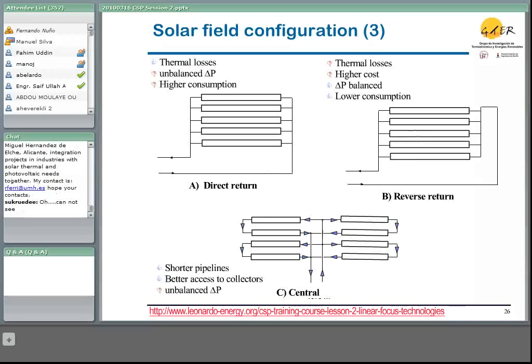The collectors can be connected to the main pipelines in different ways. Here we are showing three different ways to connect the collectors or the loops to the main pipelines. The first one is the direct return connection, which is probably very efficient from the point of view of thermal losses, but the pressure drops are unbalanced, and the oil pumps have a high consumption.